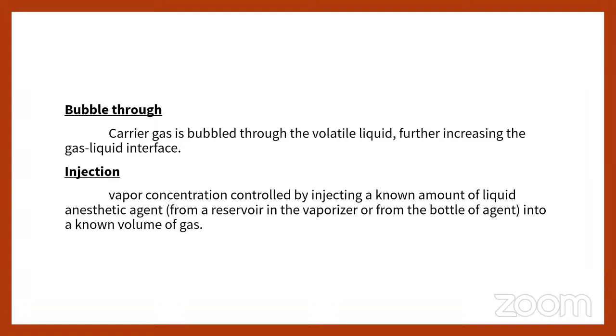And the third type of vaporization is injection. Vapor concentration is controlled by injecting a known amount of liquid anesthetic agent from a reservoir in the vaporizer, from the bottle, into a known volume of gas. Just imagine we are giving 1 liter of fresh gas to the patient, and the amount will be calculated, and the calculated amount of liquid anesthetic agent will be inserted into the fresh gas.